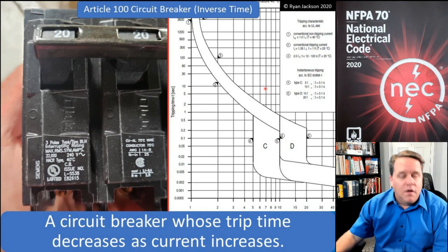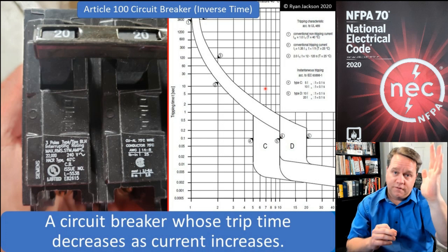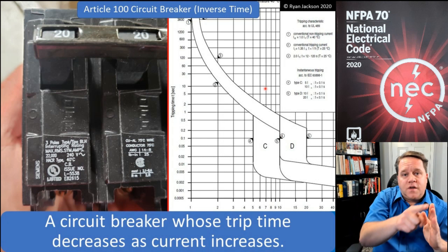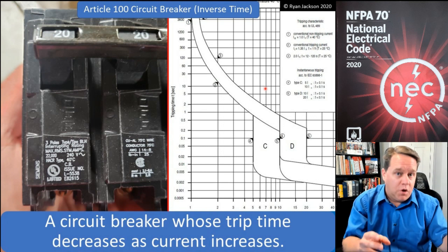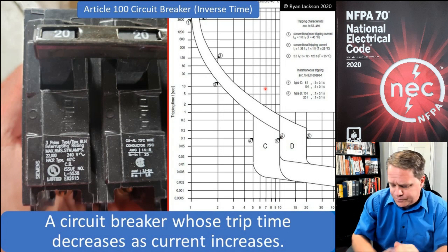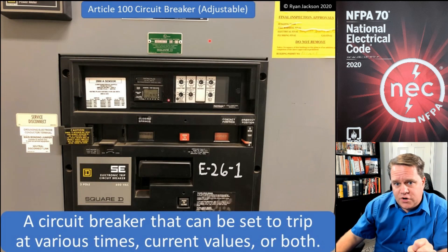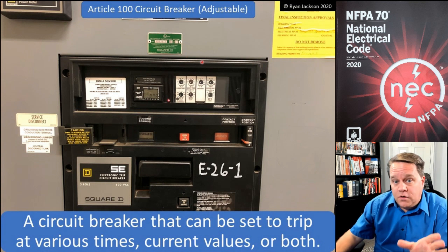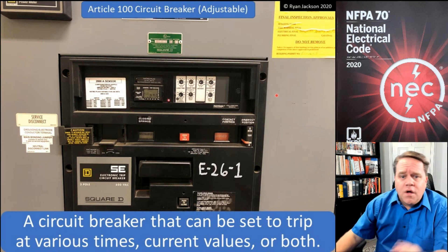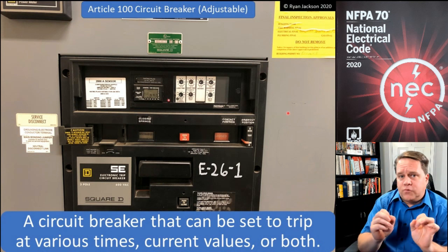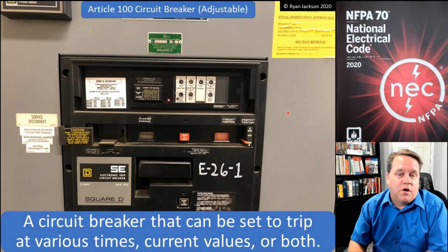With an adjustable trip circuit breaker, you manipulate what the time-current curve looks like. You set the long time pickup to the rating — that should hold indefinitely, completely vertical on the curve. Then we can set the pickup time, the ramp on how fast we want it to trip as it gets beyond that current, change the ground fault protection, and adjust all sorts of different settings. An adjustable trip circuit breaker lets us adjust both the trip points and trip times — we're adjusting the time-current curve.